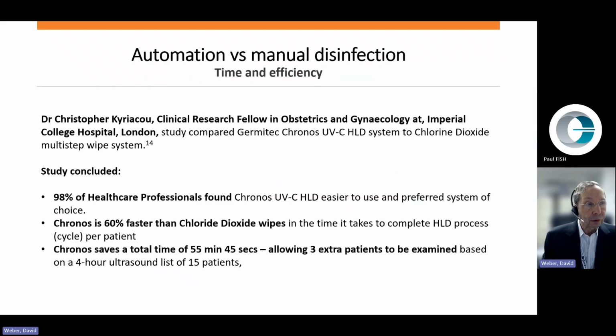Let's turn now to time and efficiency. One colleague, a clinical research fellow in obstetrics and gynecology at Imperial College Hospital, London, compared Germitec Chronos UVC high-level disinfection to chlorine dioxide multi-step wipe system. The study concluded 98% of healthcare professionals found the Cronus UVC high-level disinfection easy to use and the preferred system of choice. Further, Cronus is 60% faster than chlorine dioxide wipes in the time it takes to complete HLD processes, that is cycles, per patient. Therefore, Cronus saves a total of 55 minutes, 45 seconds, allowing 3 extra patients to be examined based on a 4-hour ultrasound list of 15 patients.